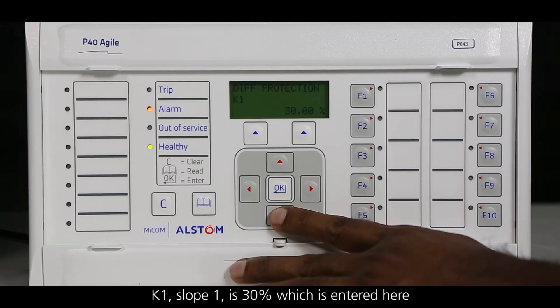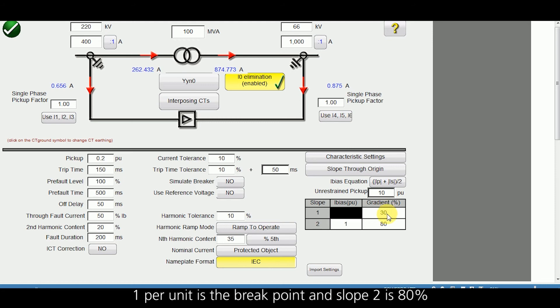K1, slope 1 is 30 percent, which is entered here. 1 per unit is the breakpoint, and slope 2 is 80 percent. The characteristics equation is I1 plus I2 by 2.